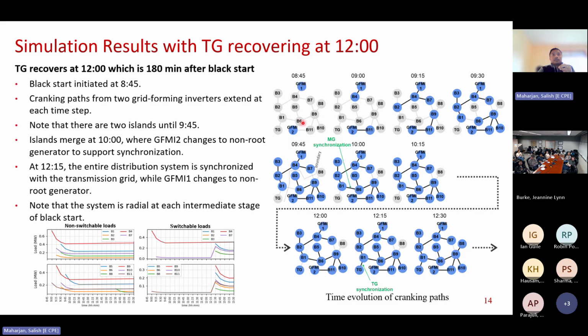So you can see that at 8:45, two grid forming inverters are started, and they help to energize the neighboring bus blocks B11 and B4, forming two microgrids. And then these microgrids expand their boundaries, right, by energizing the neighboring bus blocks, like shown here, and all the way until 9:45, the expansion continues, restoring more loads and bringing more PVs online. And at 10, basically, there's a synchronization. So the synchronization means two microgrids have been combined. And while this synchronization happens, grid forming inverter 2, which is GFMI2, changes to non-root generator. Okay, so it was a root generator before. So at 10, it gives up its root bus status for allowing the synchronization to happen.